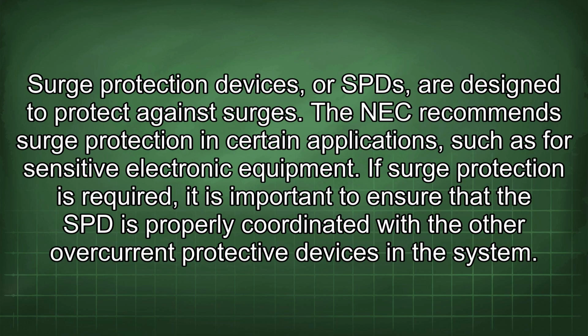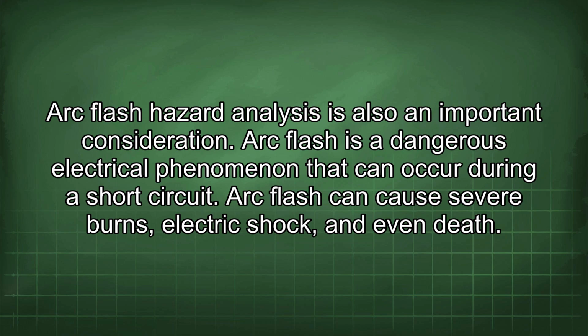Surge protection devices, or SPDs, are designed to protect against surges. The NEC recommends surge protection in certain applications, such as for sensitive electronic equipment. If surge protection is required, it is important to ensure that the SPD is properly coordinated with the other overcurrent protective devices in the system. Arc flash hazard analysis is also an important consideration.